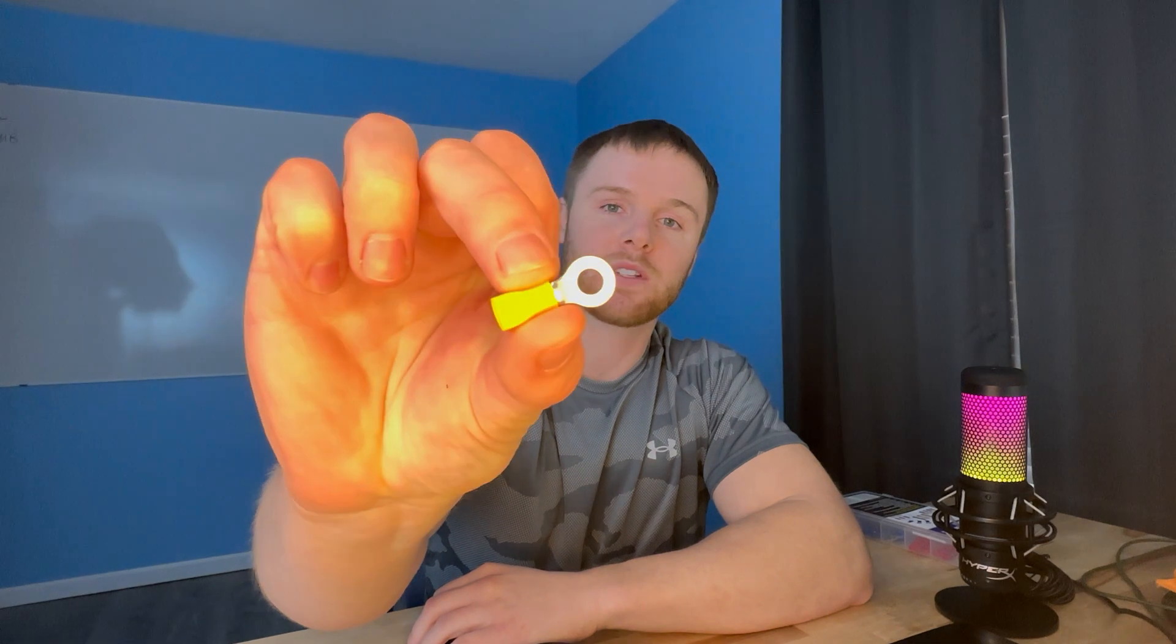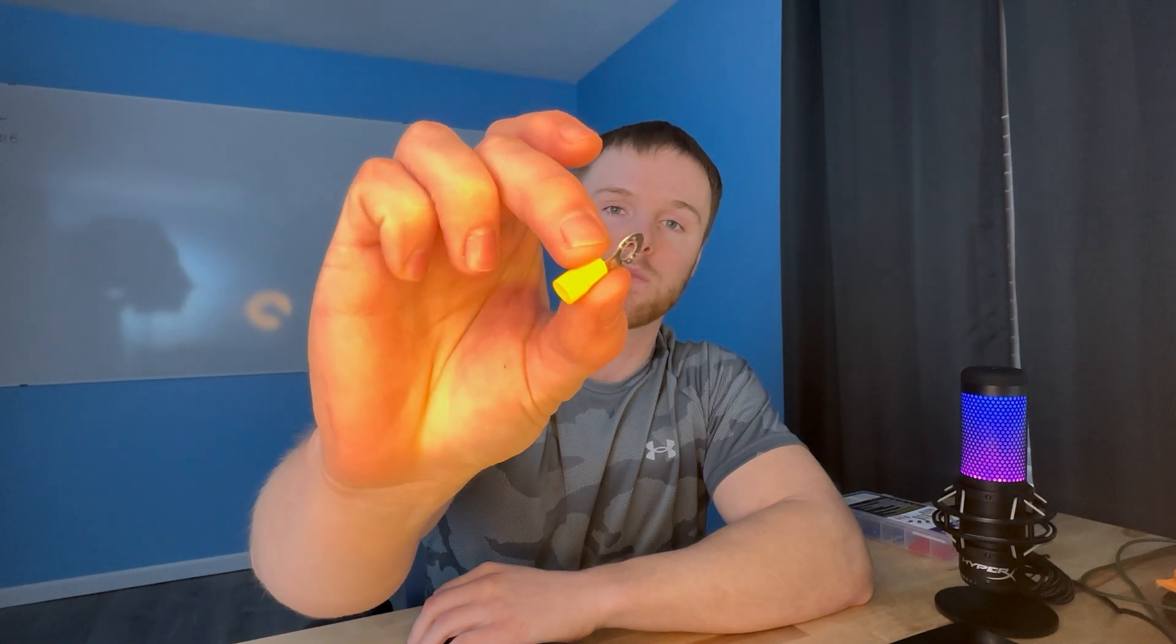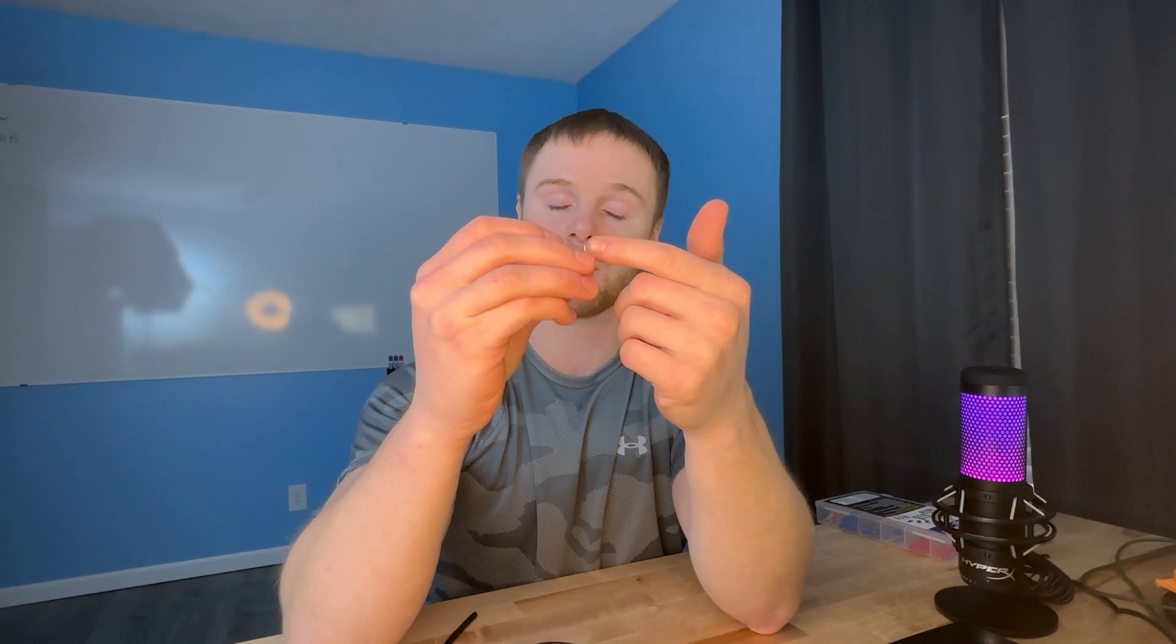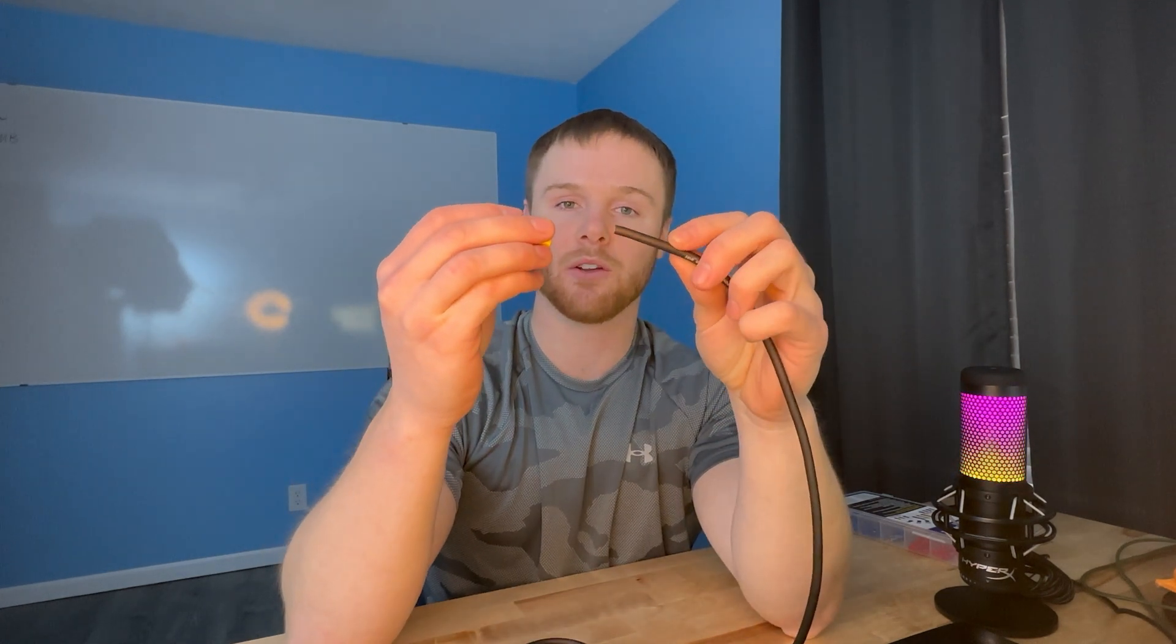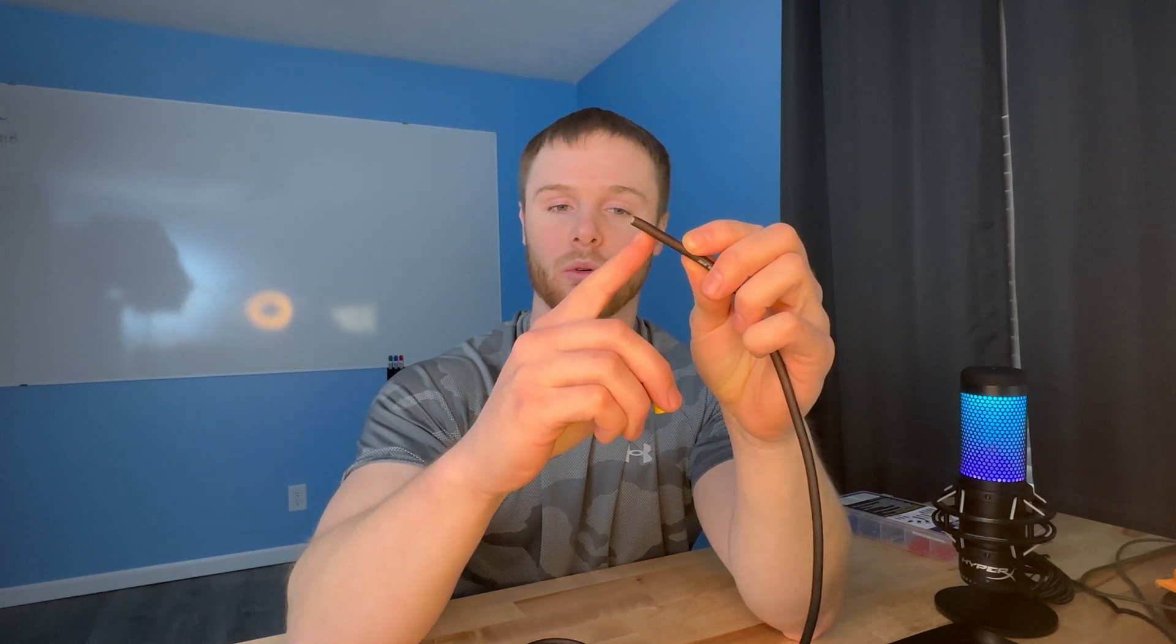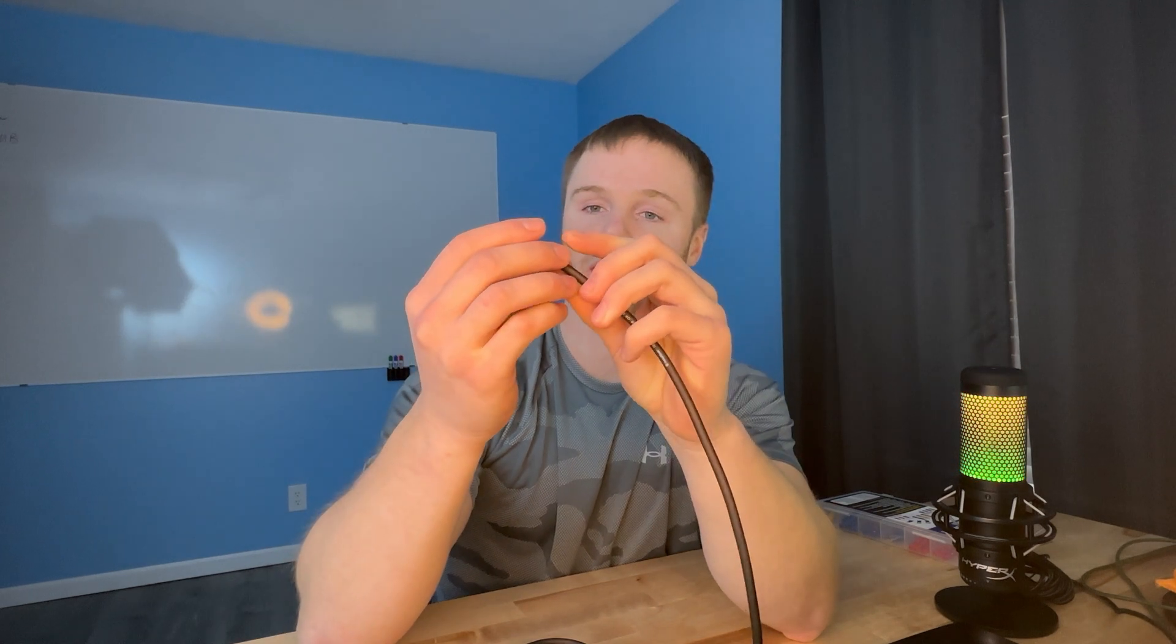Just in case any of you guys aren't that familiar with electrical, I figured I'd explain the ring terminals and disconnect pairs that we use. This is what a ring terminal looks like. You can see it has the opening that forms the ring and then has a place for you to insert your wire. This ring is gonna slide over the threaded piece of either the circuit breaker or the battery, and then you're gonna attach that with a nut on top. For the wire side, you're gonna take your wire. You need to strip back the insulation about a quarter inch and then you insert that into the back of it.